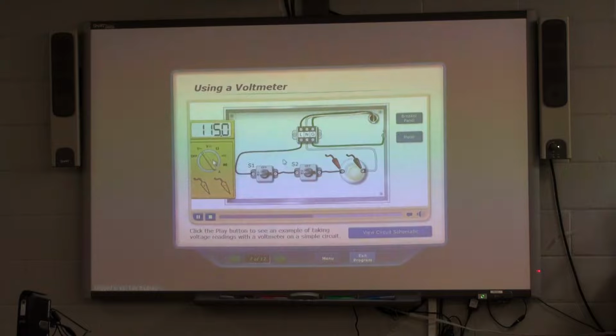If one switch is open, the light bulb is no longer energized and the voltmeter now reads 0 volts. Now, let's move one meter probe to the neutral terminal and, with the other probe, measure the voltage at each terminal. Notice the difference in voltage across the open switch. Using a voltmeter in this way allows you to measure the difference in voltage between any 2 terminals in a circuit.